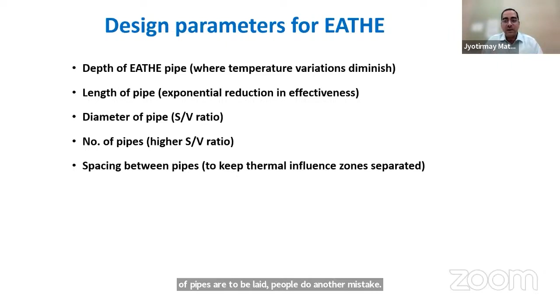But when laying number of pipes, people make another mistake: they lay the pipes very closely. What happens is, between two pipes, there isn't sufficient earth to absorb heat, so one pipe has thermal interference with another, and the system doesn't work very well. Then we have soil properties, as I already said—conductivity, specific heat, and density are most important. Material of pipe is another source of confusion. Of course, metallic pipes have more conductivity compared to HDPE, which is another alternative, but frankly speaking, if the wall thickness isn't very high, the material doesn't matter much.